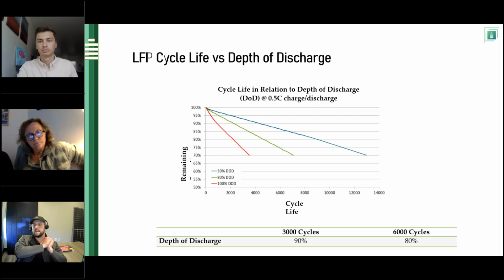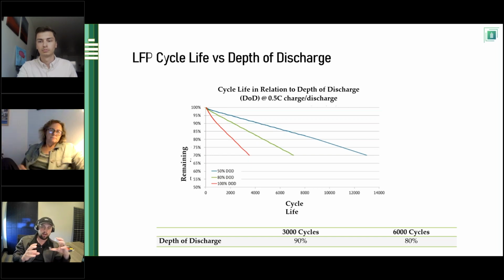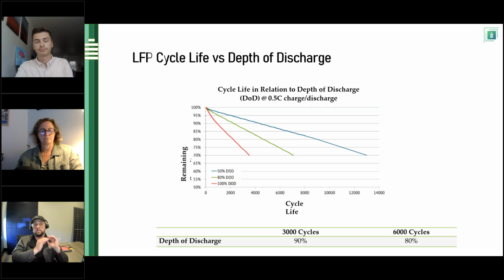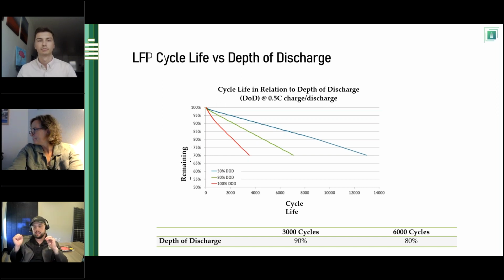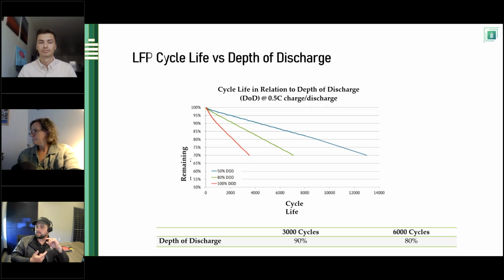We're usually going to design around an 80% depth of discharge target, because we know that during certain points in the use of the system, let's say certain times of the year, you're likely going to use less energy, and as a maximum, we're going to use 80%, right? So in the event you get to a 20% state of charge, which is 80% depth of discharge, you're going to have maybe a backup generator, or if it's grid interactive, you're going to have grid pass-through come in. But ideally, rarely are you going to hit that 20% remaining capacity, right?